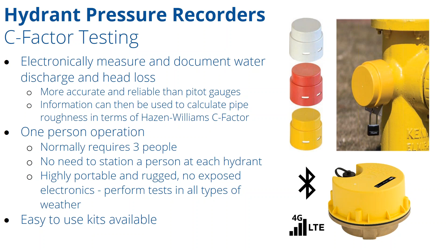This is normally a very manual process. It can take three different people to do without an electronic means of gathering this information, because it requires somebody monitoring an upstream hydrant, a downstream hydrant, and a flow hydrant to get the correct data. One person can do this with our hydrant pressure recorders, installing one on the upstream hydrant, one on the downstream hydrant, and one on the flow hydrant, and it automatically calculates the data. You don't need someone standing in front of a hydrant recording manual pressure readings; we do this electronically, and it's all stored in our software, which automatically produces the results you need. That's the C-Factor test, and we have a workflow built for calculating and providing the right information.